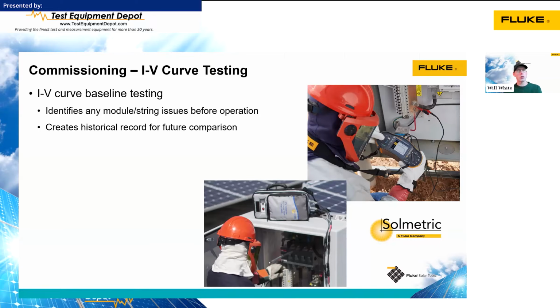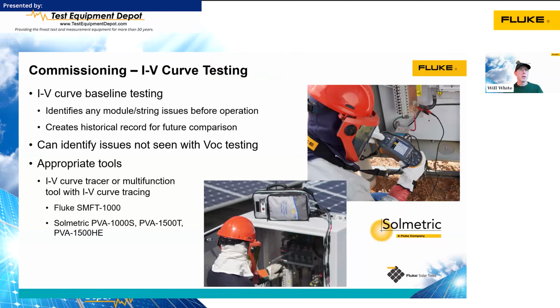The nice thing about doing IV curve testing at commissioning is it gives you a historic record, so you can ensure that the modules were working properly when the system was installed. The nice thing about IV curve testing is you can identify deviations from the IV curve that you would not find just by doing open circuit voltage or short circuit current testing. So it can find problems like notches in the IV curve, reduced slope on either the horizontal or vertical legs, reduced power point. Fluke has 3 IV curve testers in the portfolio.